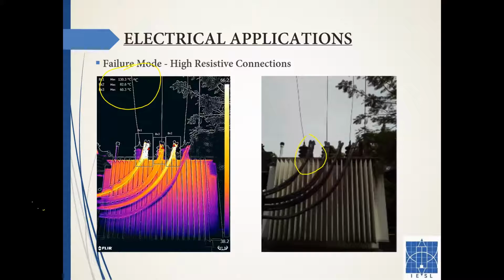So that is one application: if you see a high resistive connection. This is the most common application most engineers know. When you see something hot, you assume it's a loose connection, and mostly it is high resistive as well, but we don't know whether it's loose or maybe annealed to the terminal. It may be due to high temperature and thermal cycling, where the terminal itself and the lug can be stuck together. So if you think it's a loose connection and ask your technician to tighten it, there's a very good chance you'll make things worse. If it is a loose connection, it will be okay, but we don't know for sure.